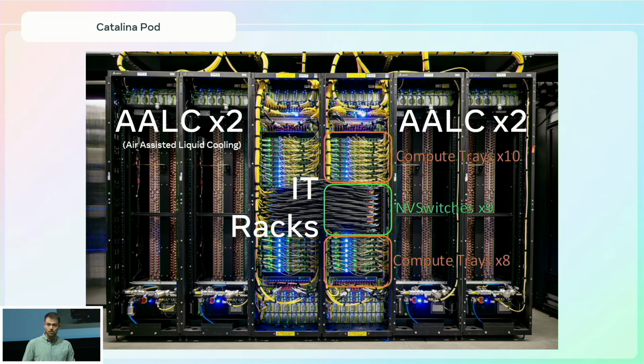AALC, you can essentially think of it as a giant radiator. You can see all the copper basically going through the rack with a couple pumps at the bottom. There's fans in the back that pass air through, and that cools the liquid, which then goes to the rack and cools the high power density IT components - the GPUs, the CPUs, the NV switches.